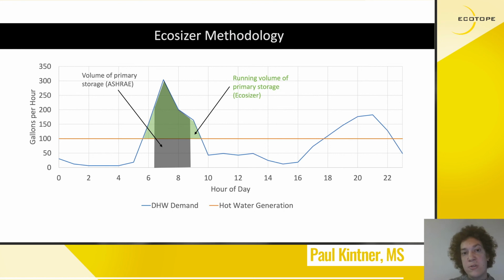And then what users get out of the tool is a recommended size for the primary system and the temperature maintenance system based on the schematic, and a trade-off curve between the primary heating capacity and the primary tank volume that accounts for this temperature maintenance load. Users can use these systems to size a system for their individual cases. And all of this software that does the sizing calculations is open source and available for anybody. In fact, Mitsubishi has already expressed interest in it for their systems.